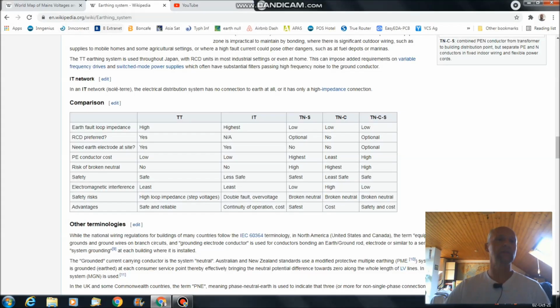Here I have a table, you can find this on Wikipedia about earthing systems, showing the 5 defined earthing systems we work with. When it comes to a grid connection, you typically only deal with 2 different systems, maybe a third: the most common are the TT system and the TNCS. In some places you might still find a TNS system. But with grid connections, you'll very rarely find IT and TNC.